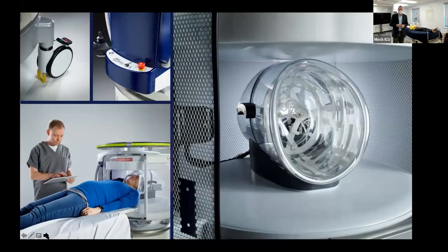Zooming in, on the lower left you see the iPad where we operate — right next to the magnet, outside of the five-gauss line. On the right side, notice the clean surfaces: two magnetic poles top and bottom, and the eight-channel head coil. In a world where we're daily, hourly, minute-by-minute conscious about infection control, the ability to wipe all of this down, go bedside into a COVID-positive patient room, and clean it out quickly before moving on to the next patient — very different than conventional MR.